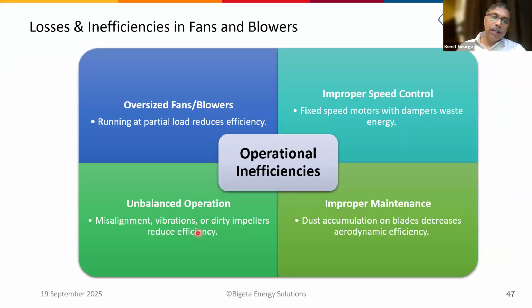Then there are inefficiencies or losses in the fans and blowers. Typically, what happens is they can be oversized fans and blowers. The same principle is applicable here also. The design will be for the best scenario, so the sizing will typically be higher in fans and blowers.